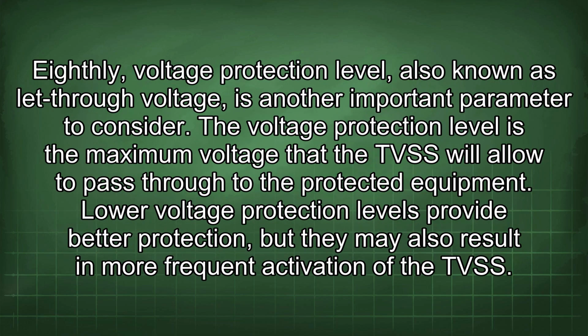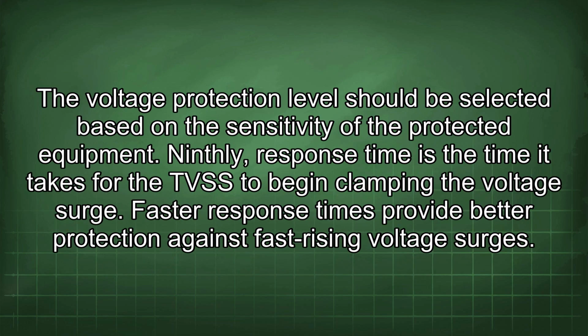Eighthly, voltage protection level, also known as let-through voltage, is another important parameter to consider. The voltage protection level is the maximum voltage that the TVSS will allow to pass through to the protected equipment. Lower voltage protection levels provide better protection, but they may also result in more frequent activation of the TVSS. The voltage protection level should be selected based on the sensitivity of the protected equipment.